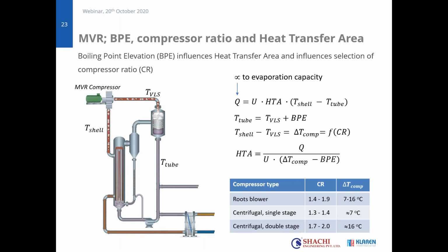But that also means that if your boiling point elevation is 5 degrees, there's not much temperature difference left to drive your heat exchanger. So what you see is that in systems that have concentrated effluents with high boiling point elevation, you're almost forced to go to a double stage. But you can also imagine, if you take into account the previous pictures, that a double stage compressor is quite an investment, and also it's a lot of machinery. So that's also from that perspective important.